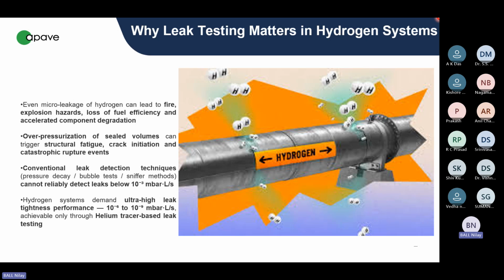So you have to use very high standard fittings. What we are trying to do to help the industry is, instead of doing 100% helium leak test, can we do a mixture of 20% helium and 80% air or nitrogen? That experimentation is being done right now. We've come up to 30% or 35%, but below a certain limit, the tests are not effective. Does that answer your question?